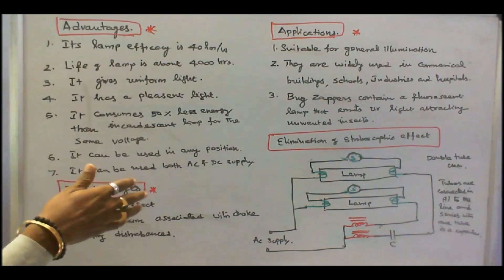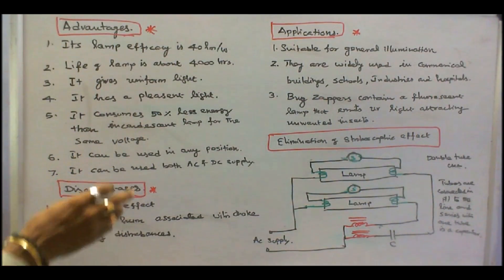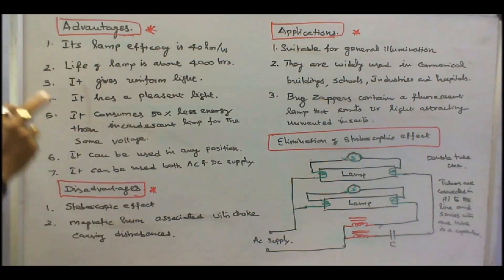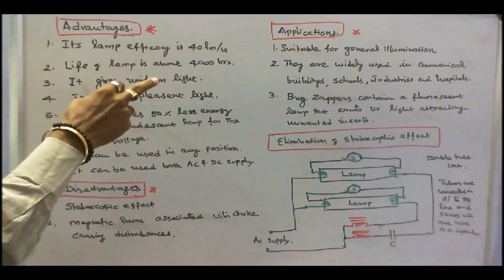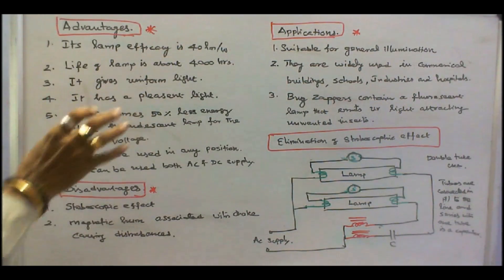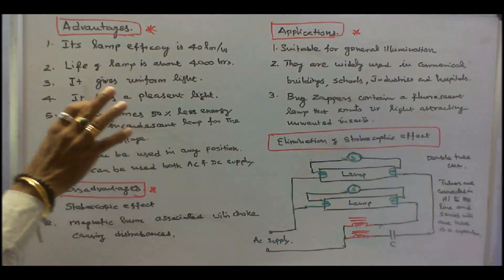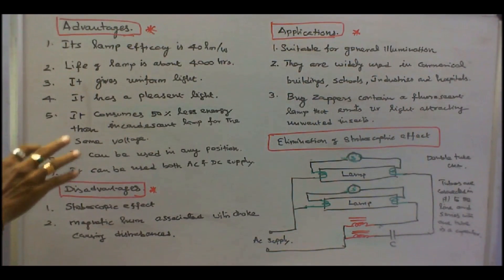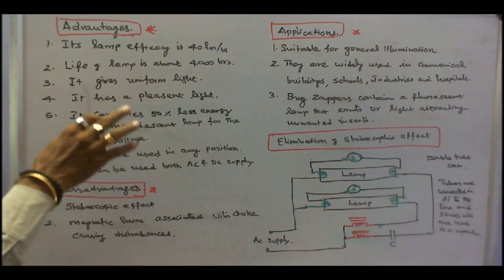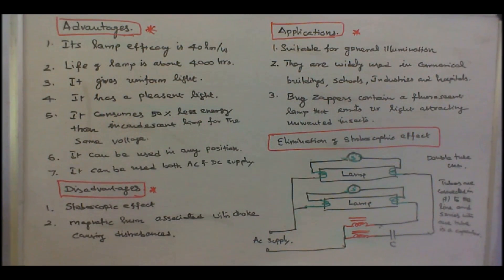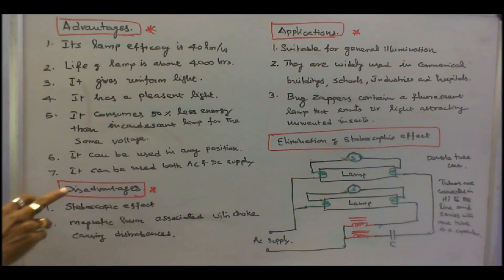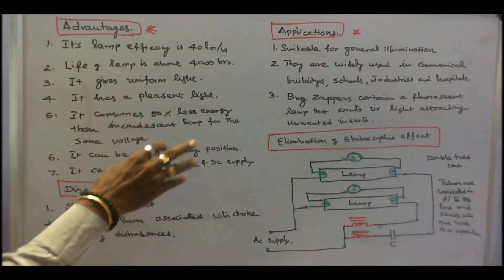These are all the advantages of fluorescent tube light. Number 1, its lamp efficacy is 40 lumens per watt. Number 2, life of lamp is about 4000 hours. Number 3, it gives uniform light. Number 4, it has a pleasant light. Number 5, it consumes 50% less energy than incandescent lamp for the same voltage. Number 6, it can be used in any position. Number 7, it can be used both AC and DC supply.